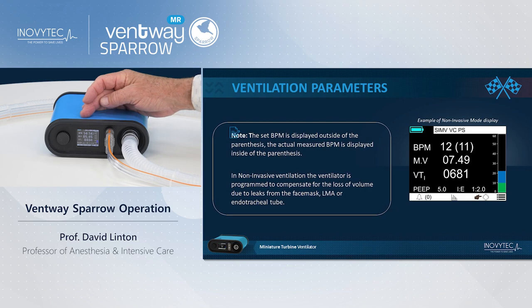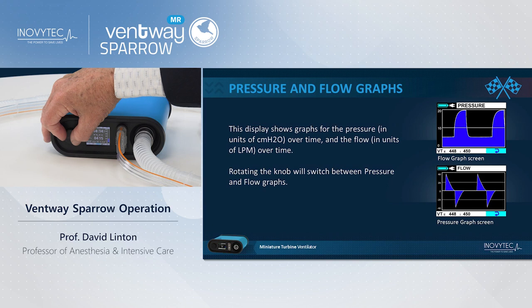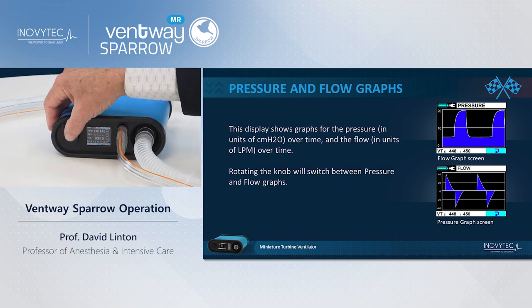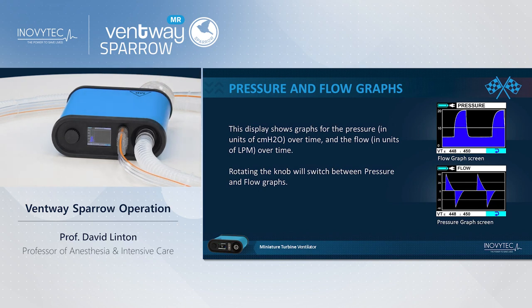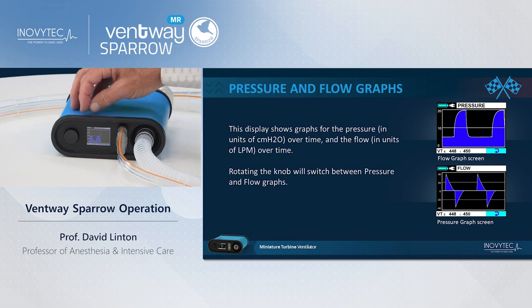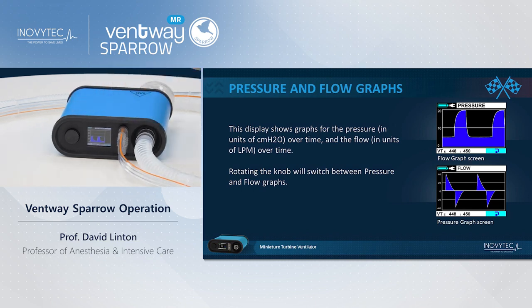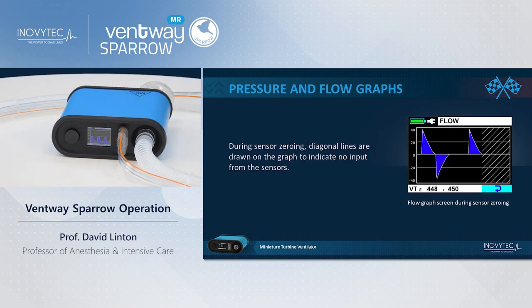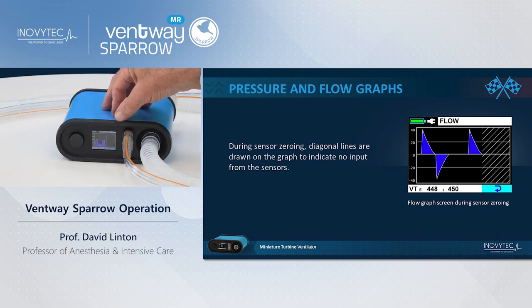If you move the cursor onto the graphic indication and you click on it, you will immediately see the pressure or flow graph coming up. And you can change it from pressure to flow, and you can see the graphs. If the sensor is being zeroed, you will see lines which indicate that the graph is not working. To go back to the main menu, you just hit return and you get back to the pressure monitoring.